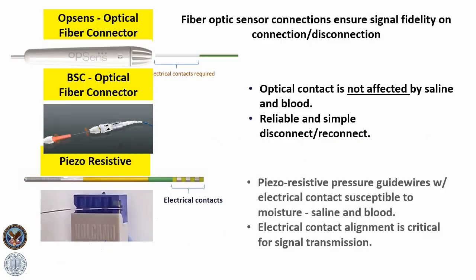All right, connections were a problem in piezo wires. If you got a drop of saline on that connector, your signal would be off, you might lose signal, and you'd have to wipe it. If you get moisture in the connector, you need a whole new system. Optical fibers do not have that problem. They see through the blood, through the saline. When they connect, they connect, and they're very stable. You can disconnect and reconnect many times. You can even bend the connector at the point of connection because it's at the end. With the piezo wires, a bend at the end of the wire can end that wire's life.